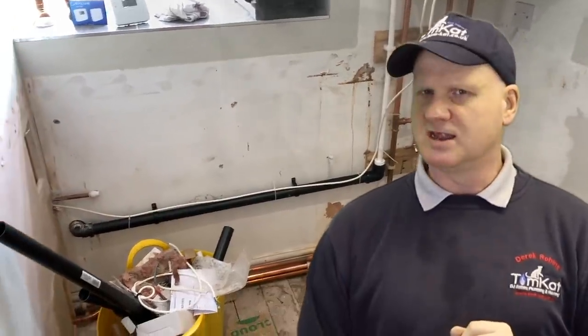So when a gas engineer is replacing a boiler or doing a brand new install, the considerations for the condensate pipe need to be really looked at. And the main thing we need to do is try and install this condensate pipe internally and run it to an internal soil stack, which is the preferred method. But they can be run into internal waste systems, such as waste coming from kitchen sinks, wash basins, baths, or even shower trays. But these wastes going from internal systems have to be a minimum of 32 millimeters in diameter.